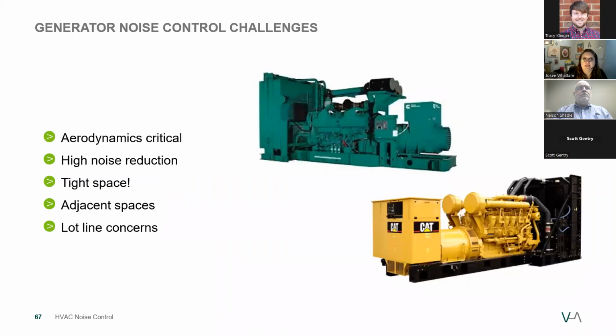I also want to discuss the noise control design challenges for generators. There are strict aerodynamic requirements of less than 0.5 inches static pressure to ensure optimal aerodynamics of the cooling air. Generators require a high amount of noise reduction due to the amount of noise they produce, which can be very costly. The generator room normally doesn't allow for much extra space, and the spaces adjacent need to be isolated correctly from the generator.